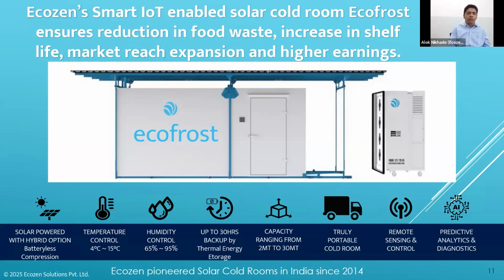To do so, we have been providing this solar PV powered solution where we can run the refrigeration system without dependence on any batteries, which increases the efficiency of power utilization. We are talking about a range of temperatures suitable for these perishable commodities, providing moisture-enabled relative humidity so there is no weight loss, and providing assurance that temperature will be maintained even when there is a power deficit.